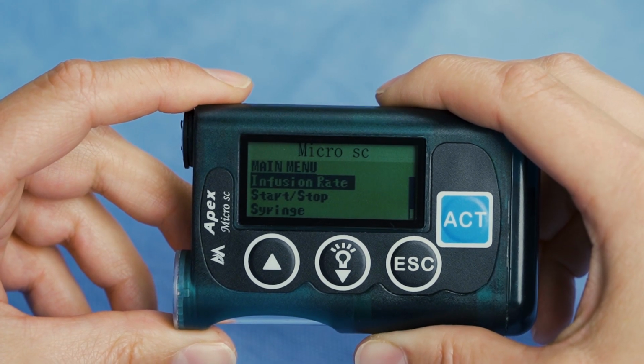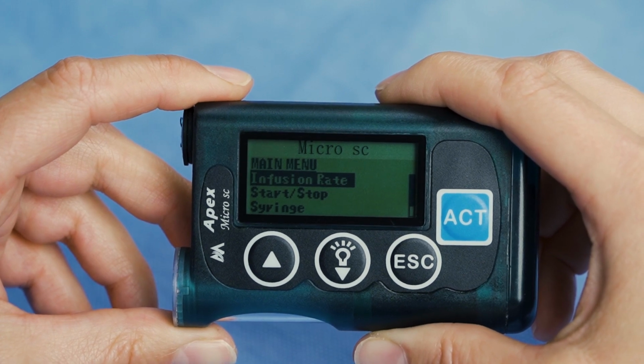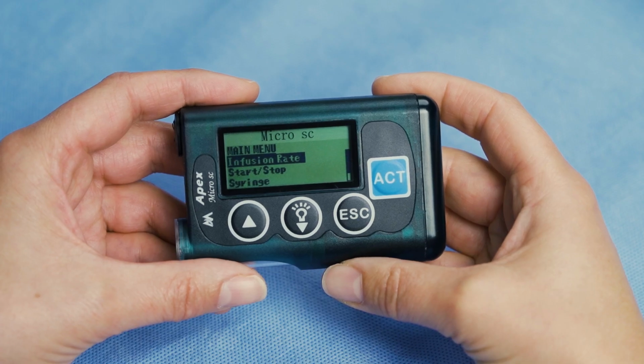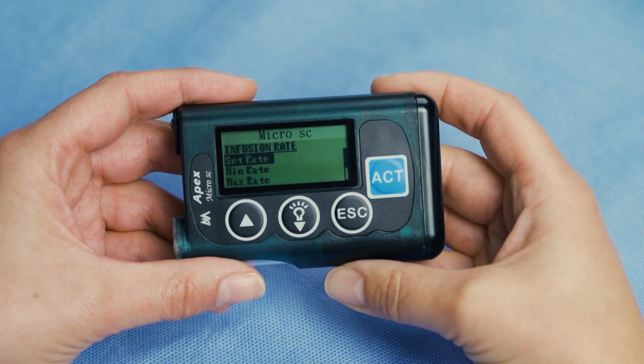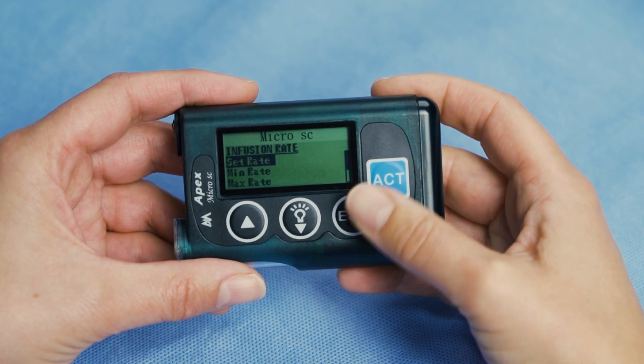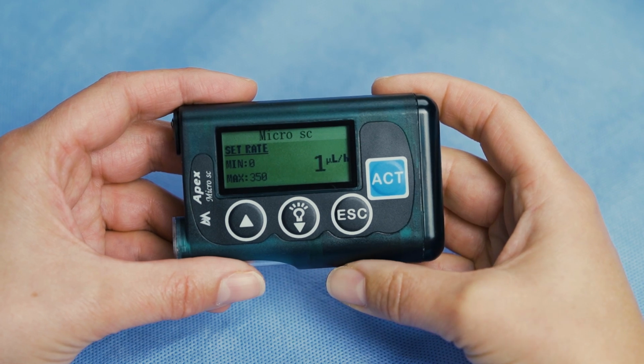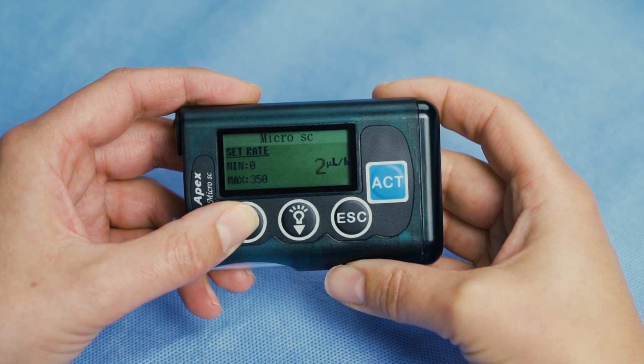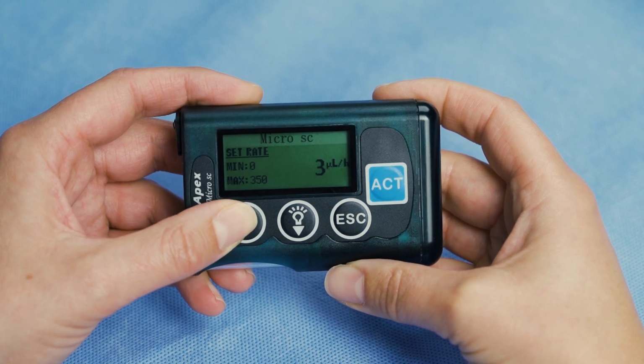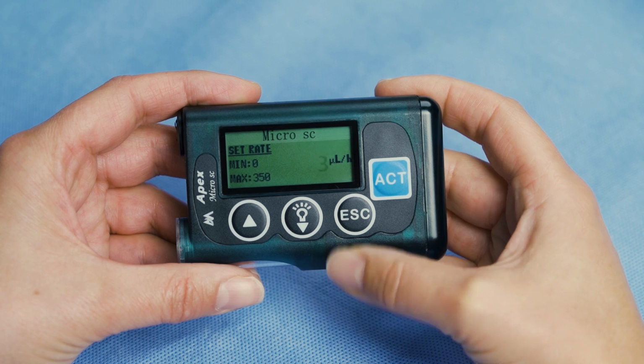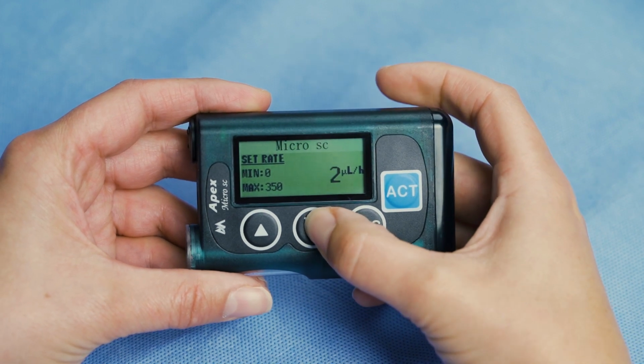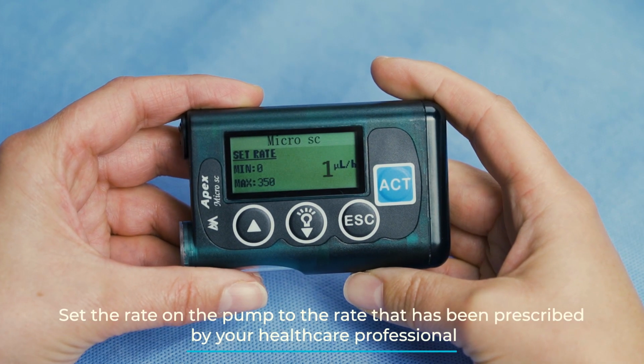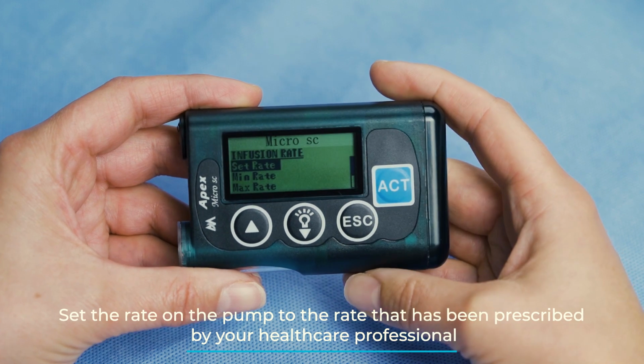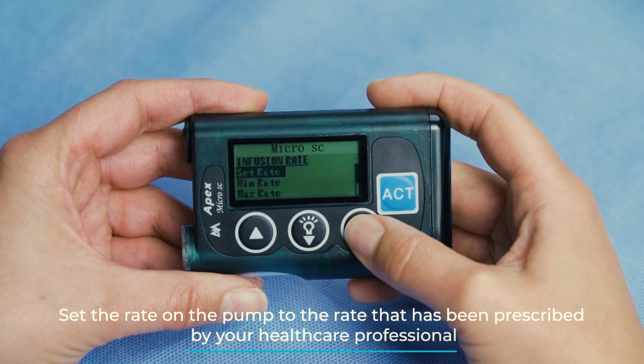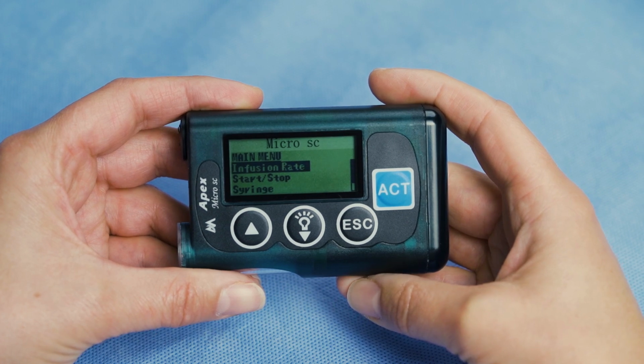The first option, infusion rate, will be highlighted. To be able to see the rate, you need to press Act. Select the first option, infusion rate, by pressing Act, then press Act again on Set Rate. Now you can see the rate in microliters per hour blinking. You can increase or decrease the rate by using the up and down arrows. Set the rate on the pump to the rate that has been prescribed by your healthcare professional by pressing Act to confirm the rate and Escape to return to the main menu.